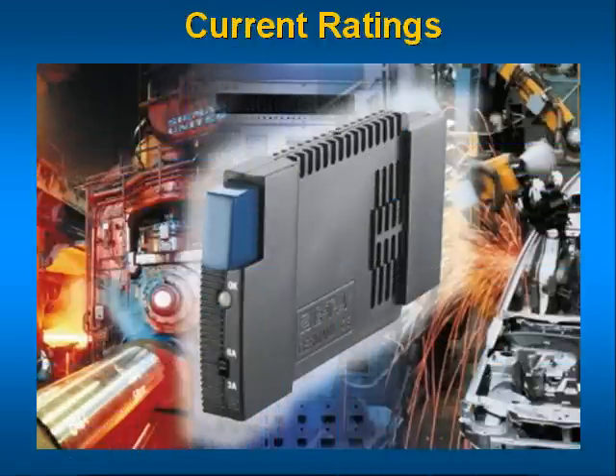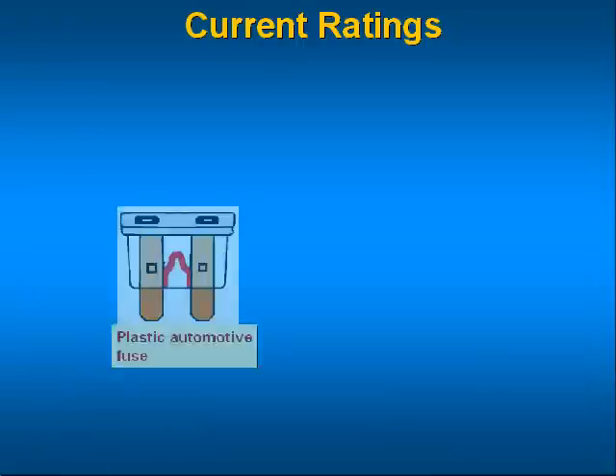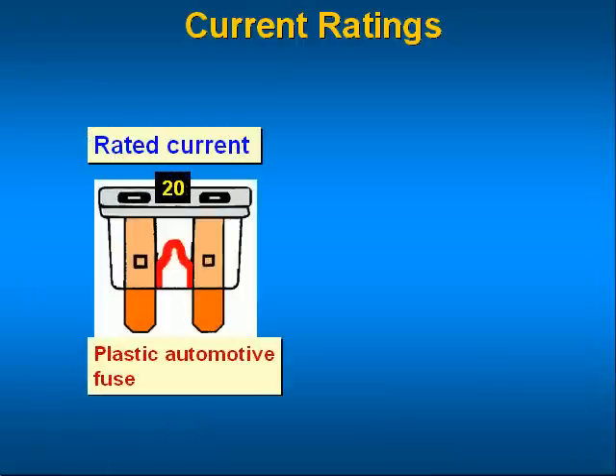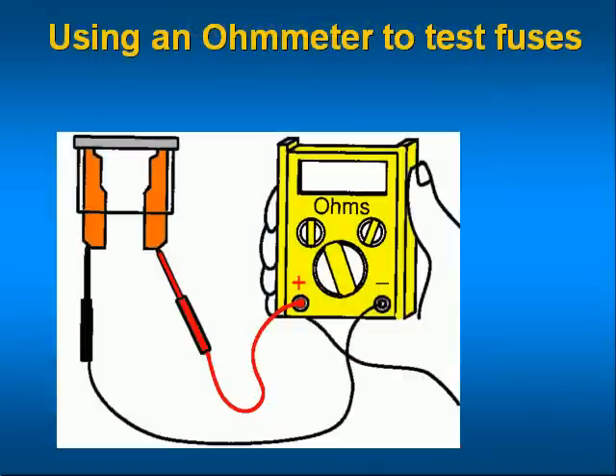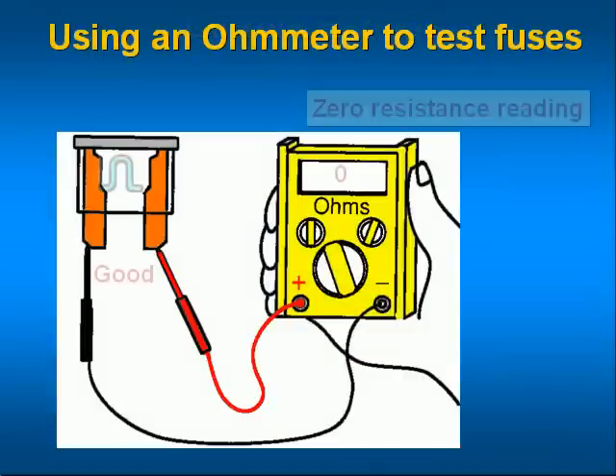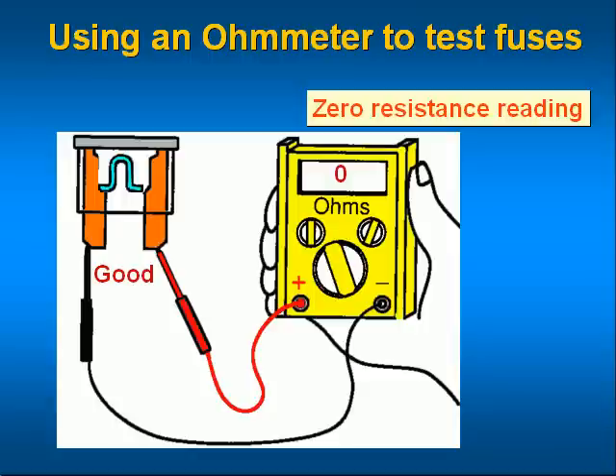Current and voltage ratings of fuses and circuit breakers are normally written on the component. The key parameter is the current rating. A fuse with a higher voltage rating can be used in a lower voltage circuit, provided the current rating is adequate. A reading of zero ohms means the fuse is good; an infinite reading means the fuse is bad.